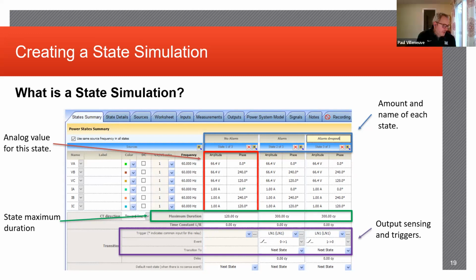If I could just add, remember, please, these are secondary currents, not primary currents. A fault current on the secondary side could look like 2 amps, but that could be 75,000 amps when you factor in the CT ratios. So all those values that they're injecting, you see the 1 amp, that actually could be equivalent to a fault on the high side, but the relay can't tell. That's just a secondary. Keep in mind the secondary has a nominal rating of 5 amps, and anything beyond that would typically be considered a fault condition, but not necessarily. On the ground, you typically set it much more sensitively, so having 1 amp for ground is a pretty common one. And you may or may not need the low voltage. It just depends on how you polarize the elements.